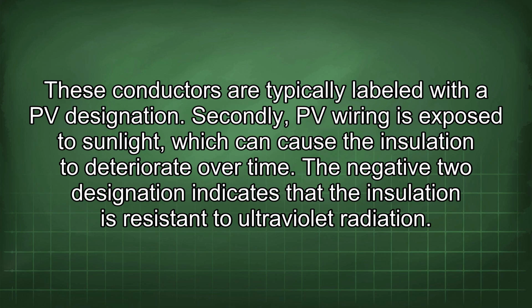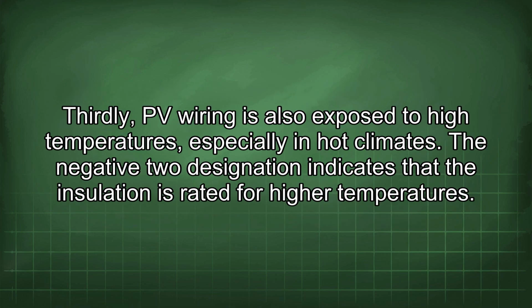Secondly, PV wiring is exposed to sunlight, which can cause the insulation to deteriorate over time. The -2 designation indicates that the insulation is resistant to ultraviolet radiation. Thirdly, PV wiring is also exposed to high temperatures, especially in hot climates. The -2 designation indicates that the insulation is rated for higher temperatures.